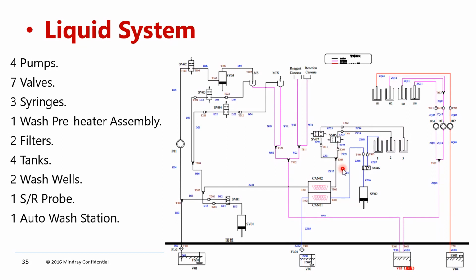Okay. So you have to verify whether the dispensed water is adequate or not. Sometimes water dispensing may not be proper, and because of that the cuvette wash will not happen properly. So you need to check these lines and valves. Okay. SV05 and 07 are responsible for dispensing water, and syringe 01 also. And the same syringe is responsible for washing the sample probe externally.